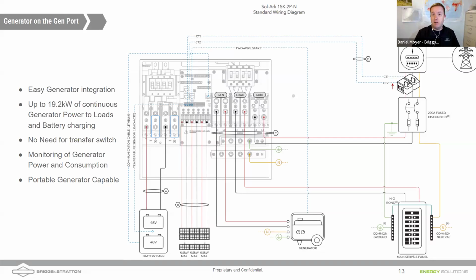All Sol-Arks and a lot of the hybrid inverters are very similar in their architecture. They have a bidirectional grid port, a load out port, and additionally a gen out port, which can also function as a gen input. So we're showing here the generator. Now that looks like a portable generator, but it could be a portable or a standby as well. And then we can control that generator using the two-wire signal to start. We're going to show you here in a minute how to adjust the value at which the state of charge of the batteries will either trigger that generator to start or to shut off. And again, you don't need the transfer switch.